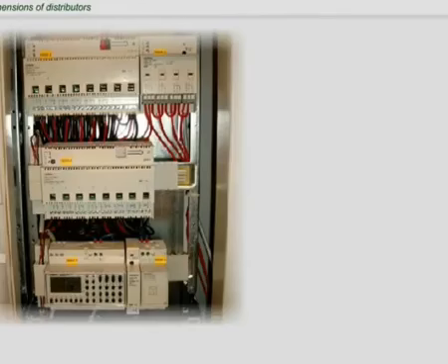Devices with higher power losses should be positioned in the upper area of the hub. In order to increase the clarity of the layout, we recommend arranging bus users and conventional high voltage current devices in separate fields. When planning the installation, the required mounting space must be calculated. Here, the following standard values are valid.